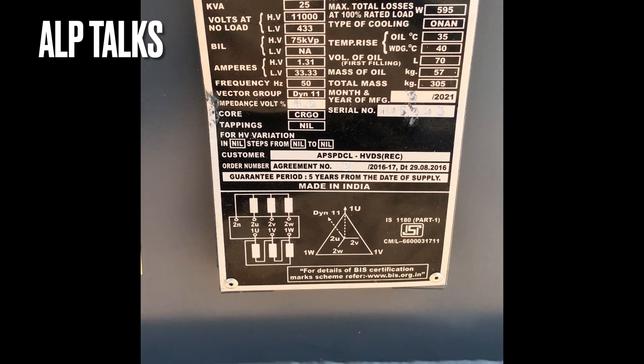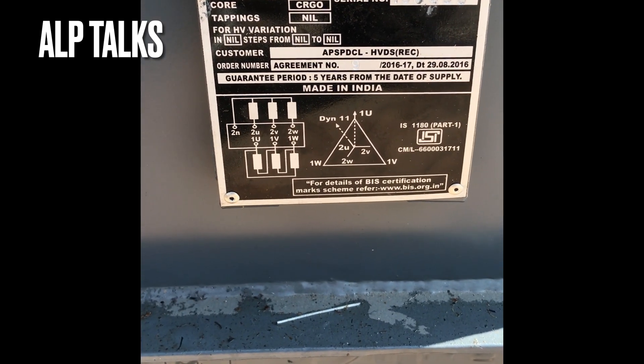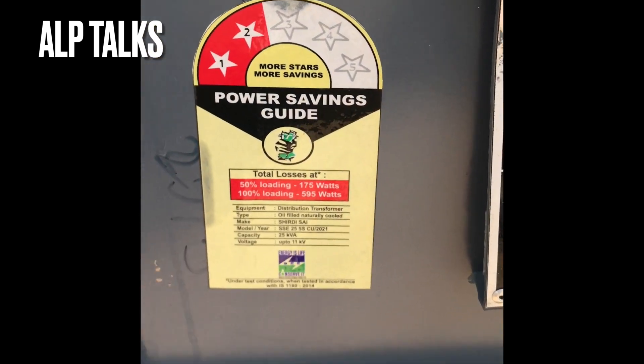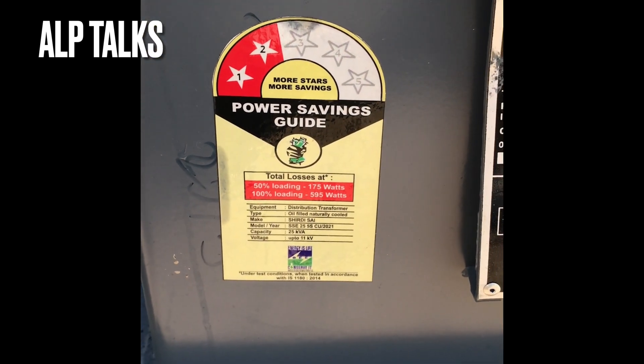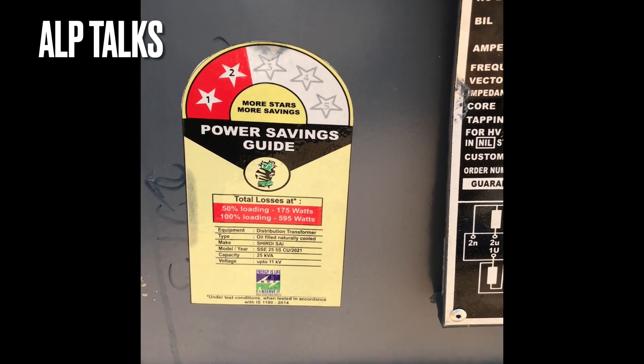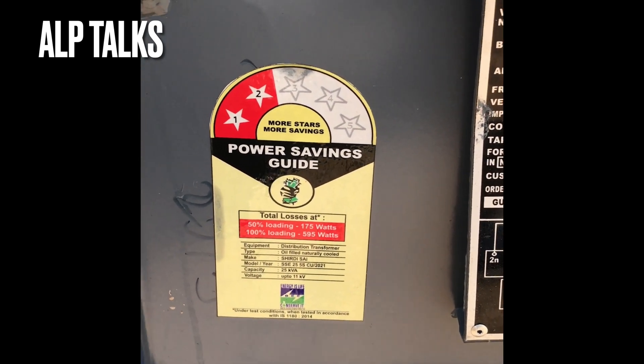This is of Shirdi Sai make. You can observe the vector group and all. This transformer is complying with IS-1180. You can observe here it is of 2 star rating — so we have a 5 star rating system and for this transformer it is 2 star, BEE 2 star.